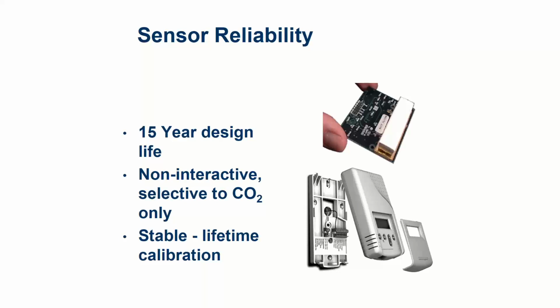The sensors would drift a lot, and then they had to be constantly calibrated. That has been a non-issue since maybe like 2005 or so. All the manufacturers have what's called automatic baseline calibration, ABC logic. So they calibrate themselves, and almost all of them, at least the ones for commercial use, can no longer be calibrated. We've removed the calibration buttons off the sensor. Because the problem was, what you normally had to do is hook up a can of gas to the inputs on the CO2 sensor, run your gas through it, basically zero it out, and then press the button to say you zeroed it out, right?